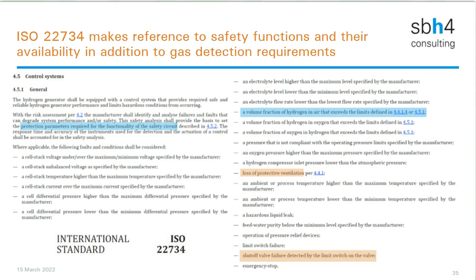So there needs to be condition monitoring of those ventilation systems to say, yes, this fan is still available, should it be required. So the whole concept of probabilities of failure on demand, or the availability of that safety function, applies to the gas and flame detection system and the safety function that it may invoke. And these are some of the things that are explained very, very clearly in this particular ISO standard related to hydrogen electrolyzers.